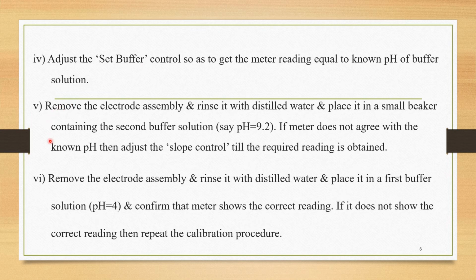The next step is to remove the electrode assembly, rinse it with distilled water, and place it in a small beaker containing the second buffer solution, say pH equal to 9.2. So in this step, what we have to do? We have to remove the electrode assembly from the first buffer solution, that is pH equal to 4. After that, we have to rinse the electrode assembly with distilled water. Then we have to take the second buffer solution of 9.2 and insert the assembly into it.